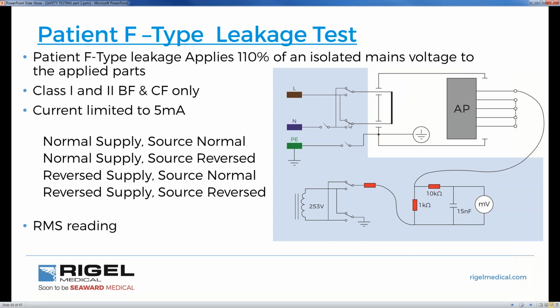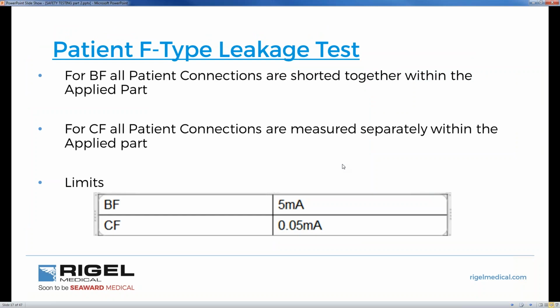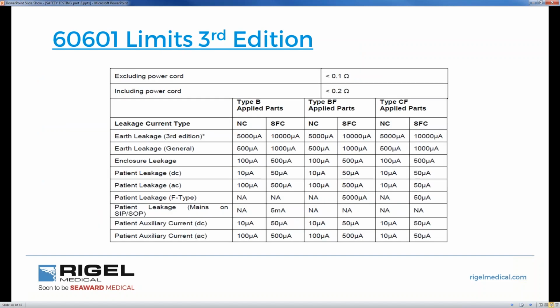And then again, we have a number of relays that open to satisfy the single fault conditions. Those are our pass-fail limits for BF and CF. For BF, all patient connections are shorted together within the applied part. Again, the Rigel does this for you. For CF, all patient connections are measured separately within the applied part. And here are our pass-fail thresholds for 60601 3rd edition. I'll just leave that on the screen there for you to take in for a couple of seconds.